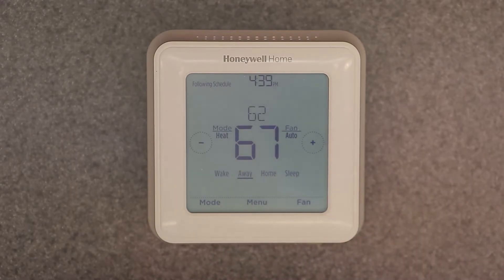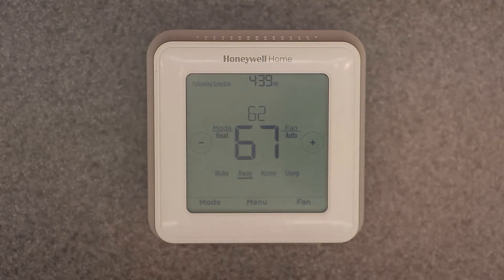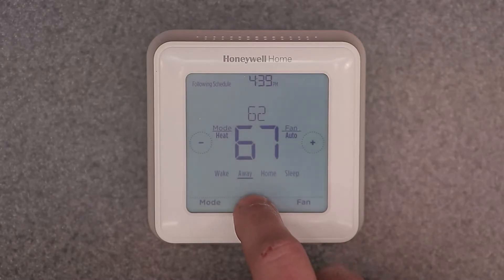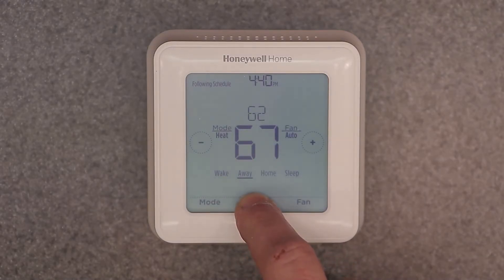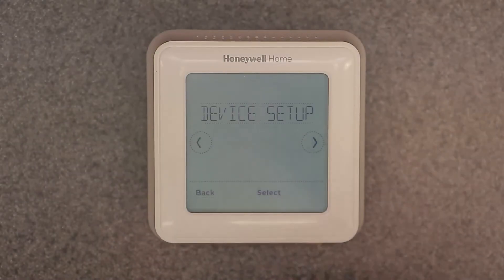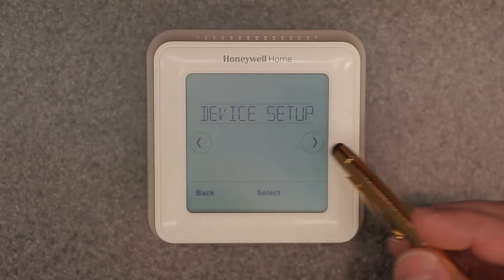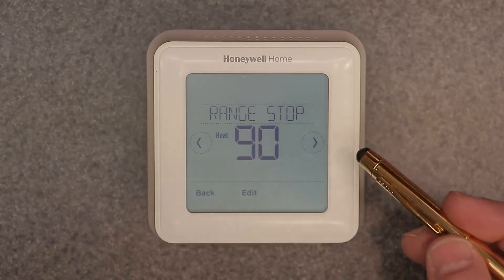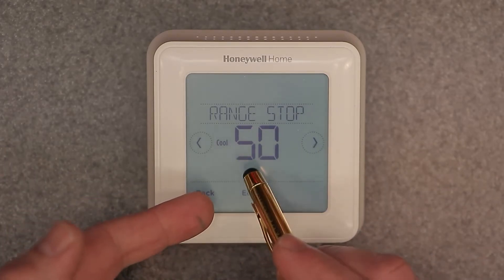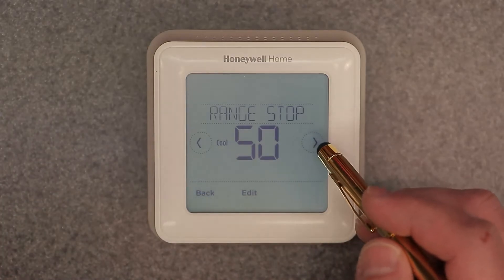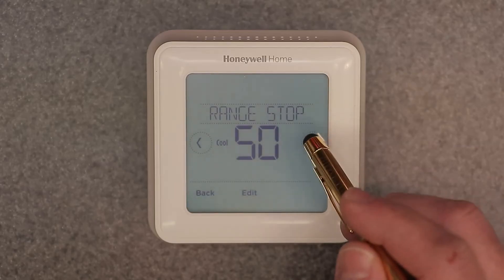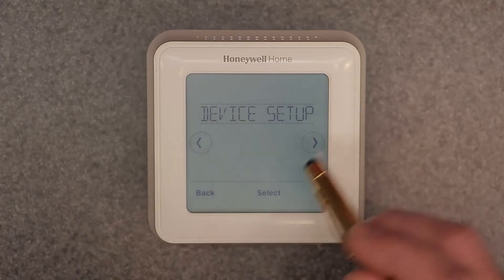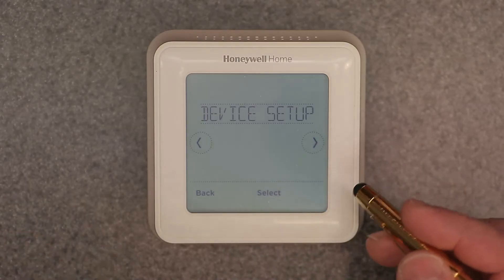Now let me show you the hidden advanced menu with the actual setup options, which is very important to do initially when you install this thermostat. Press and hold the menu button for more than five seconds. You'll see device setup, screen lock, system test, reset, range stop for heat — where you can set a maximum — and range stop for cooling, where you can set a minimum.